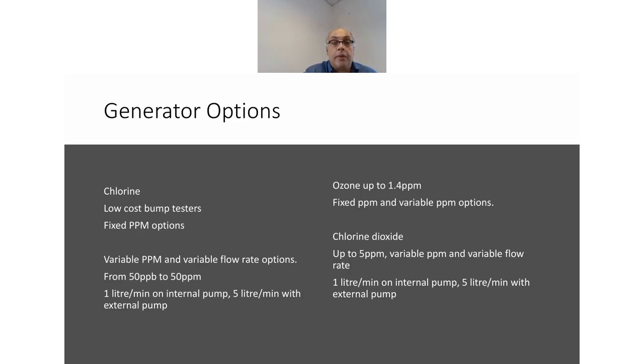Very useful. I just thought I would talk about the options again with regard to chlorine, ozone, and chlorine dioxide. To summarise what Kurt presented, there's a wide range of options from ACD for chlorine. There's very low cost bump testers, which can be converted into very low cost generators. These are handheld, in fact pocket sized options, but they are fixed in their ppm output. They're not variable, so you will have to order the ppm that's of interest to you. In many ways, like a cylinder, it will give you one output.